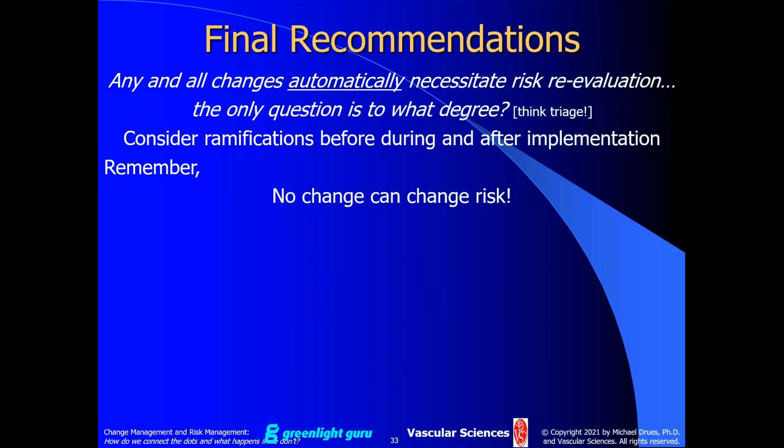Remember, not making a change also can change a risk, because if there is post-market surveillance data out there, if there is real-world evidence out there, if there are complaints, if there is information from your competitors, and you're not routinely looking at that information, and as a result you don't change your medical device to, for example, mitigate that risk that's known today that might not have been known a year ago or 5 years ago, the risk of your product is actually now increased because you have not implemented that change.